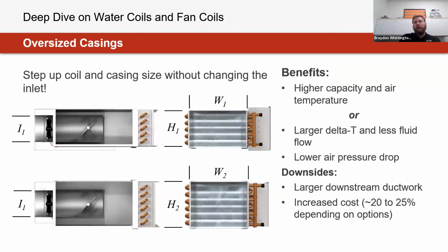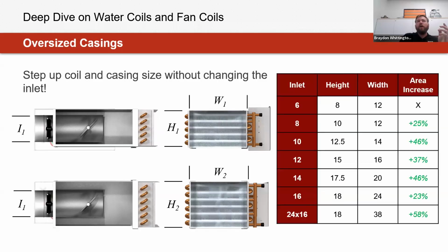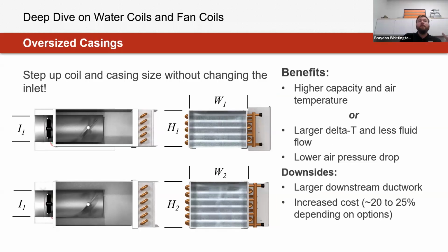Another option, when looking at a single duct level, is oversized casings. Oversized casing essentially means that you're keeping the same inlet size but bumping up to the next casing size. This could be an effective solution, especially as you start to see lower and lower water temperatures utilized within systems, because we're able to keep the same inlet size of that product. So whether our minimum ventilation calculations have been determined, we're able to maintain that. But now we've got a bigger coil that we can play with.